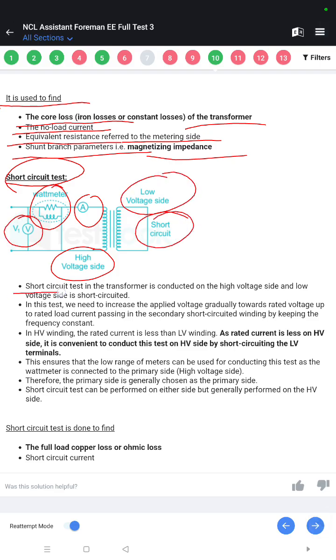The short circuit test in the transformer is conducted on the high voltage side, and the low voltage side is short circuited. In this test, we need to increase the applied voltage gradually towards rated voltage, up to rated load current passing in the secondary short circuited winding, by keeping the frequency constant. In the HV winding, the rated current is less than in the LV winding. It is convenient to conduct this test on the HV side by short circuiting the LV terminals.